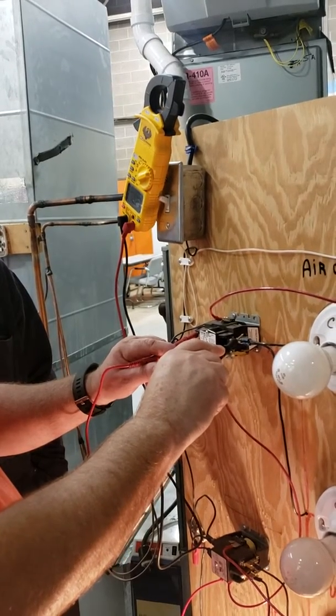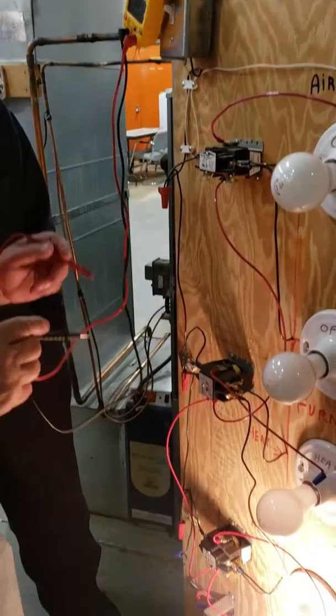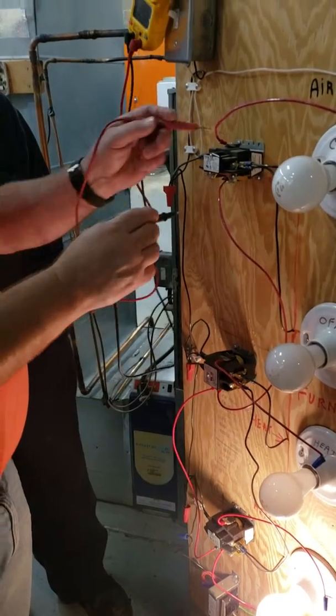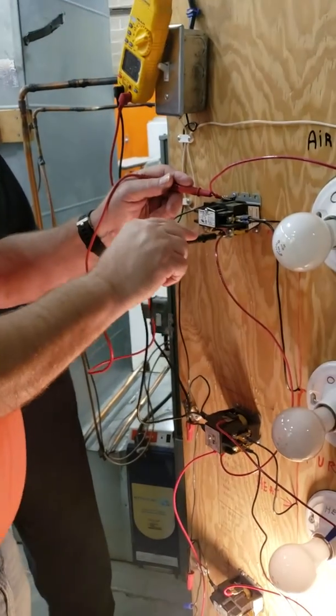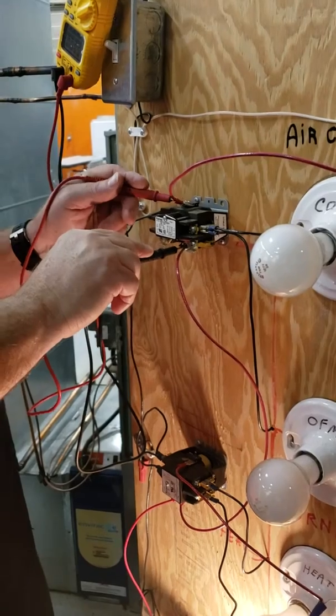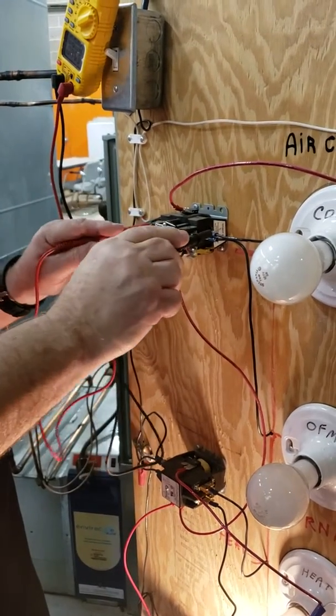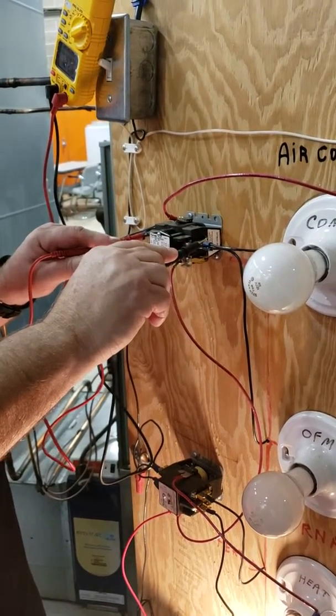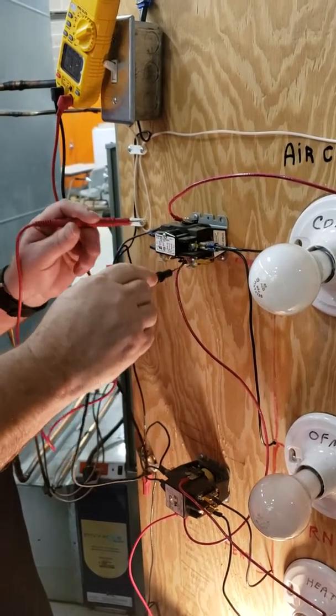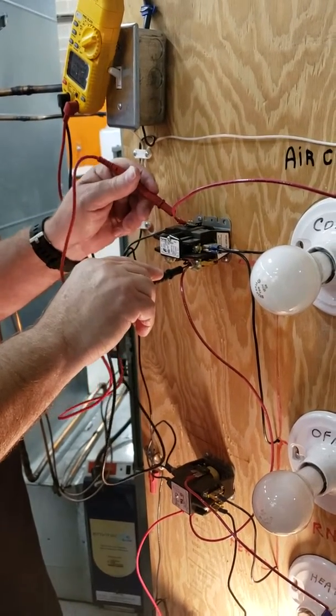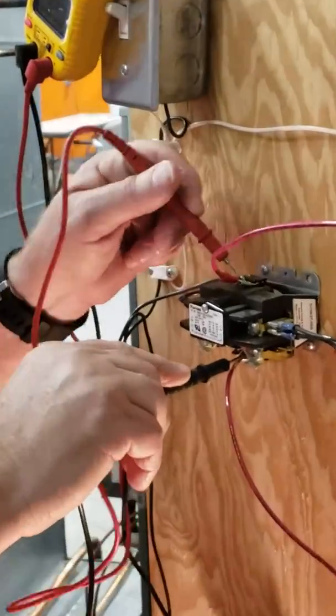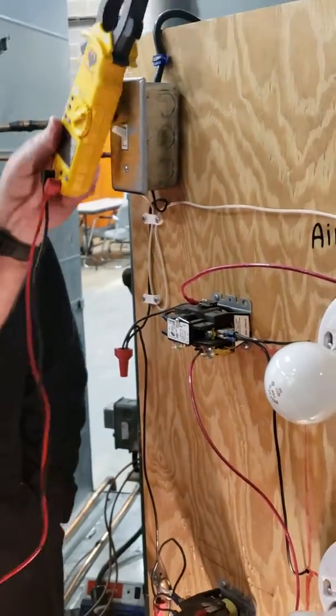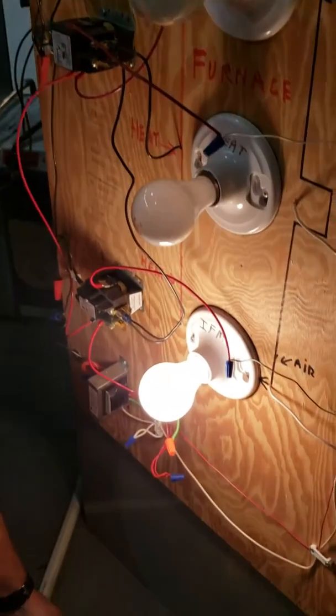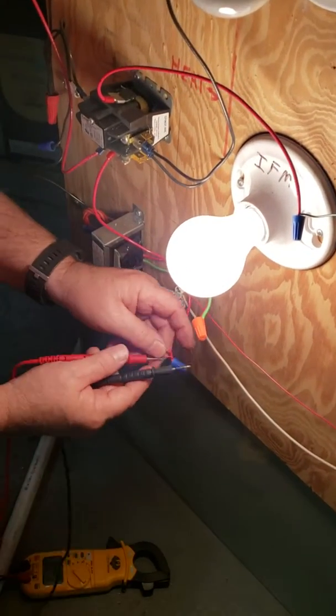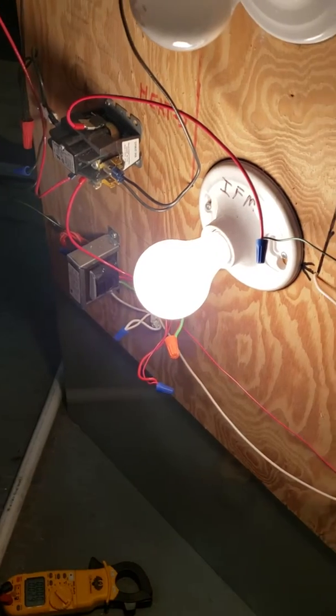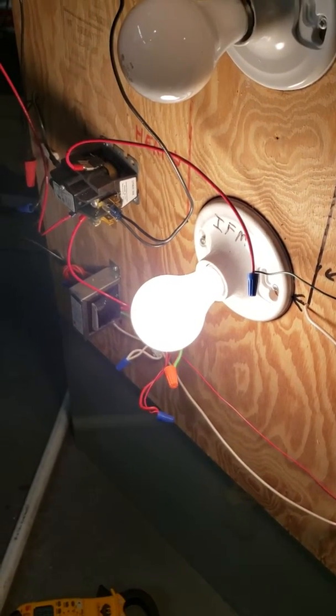I would go down and check your low voltage. Well, here's what I would do. I would check the coil to see if there's power to it, to tell it to close. So I've got an open set of contacts. I'm checking for power to that right now. I don't have power to it, do I? So it could be my transformer. Let's go my transformer. Let's see if I have power on my transformer. Here, somebody else check power on the transformer. Go ahead.